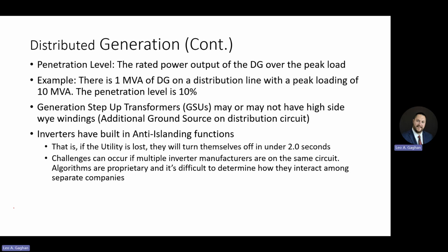Something that may not have been thought of at first when it wasn't as popular, but challenges are actually starting to occur with the magnitude of inverters that we have out there, where their algorithms are so proprietary that one inverter manufacturer can't tell if it's islanded if it's connected to a different inverter manufacturer, right? It can't tell the difference between the other inverter and a normal grid. So we're starting to run into challenges where having multiple inverter manufacturers on the same circuit may actually hold each other up and prevent the anti-islanding functions from working and forcing them to turn themselves off in under 2 seconds. So that's starting to become, I guess, a challenge.